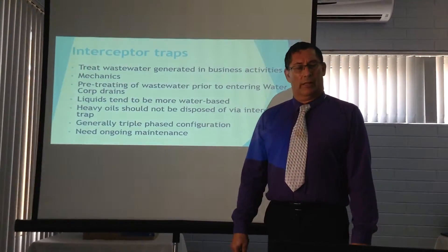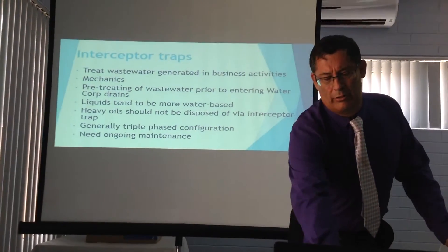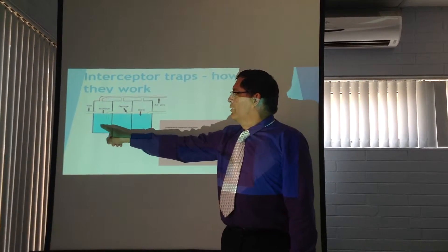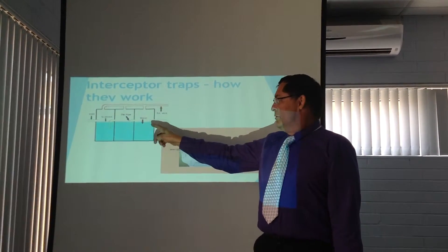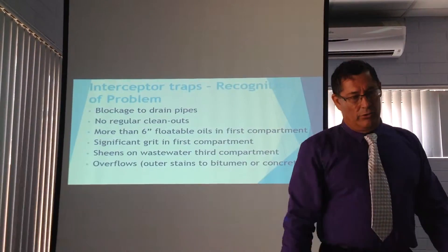Typically there is what we call a triple phase configuration — a system of three compartments that require ongoing maintenance. If I was to cut away a side view of an actual interceptor trap, you'd see the wastewater stream coming in: the first compartment allows the grit to fall to the bottom and allows oil buildup to occur, with the rest of the stream overflowing. The second compartment should be mostly water with no grease. It then overflows to the third compartment, which should be almost all water — no sheen, no oils, no grease. That's the normal operation of an oil interceptor.